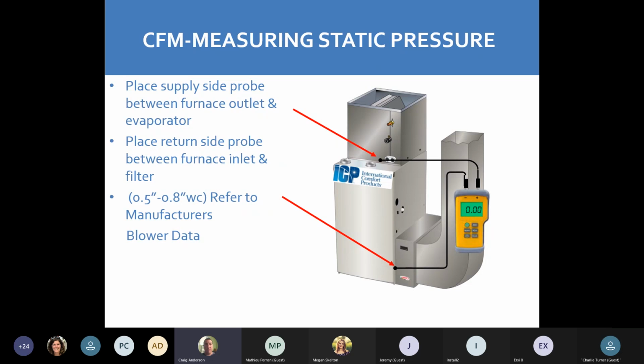If you're going through motor failures on a furnace constantly, or high limit problems in the wintertime, and now we're having freeze up coils in the summertime, check your static pressure. If that is on, then we're taking that out of the equation. Our airflow is good. We need to look at fan speeds. We need to look at something outside the box. So two main things: static pressure. Make sure you got the proper charge in your system. Great two things to get out of the equation.